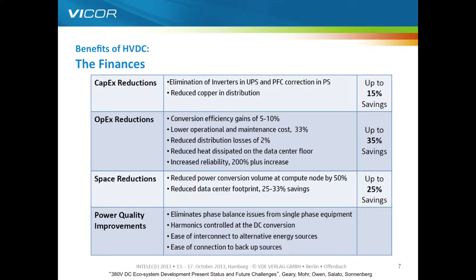And a difficult one to quantify, but definitely power quality is a huge bonus for high voltage DC. If you take three-phase AC into the edge of a building and then convert down to high voltage DC for the rest of the transportation and conversion of that power, you don't need to worry about phase balancing or any lost or abandoned power that you'd have in a typical three-phase system. That's where high voltage DC makes a lot of sense and makes things very simple.